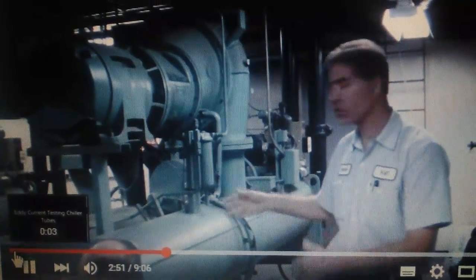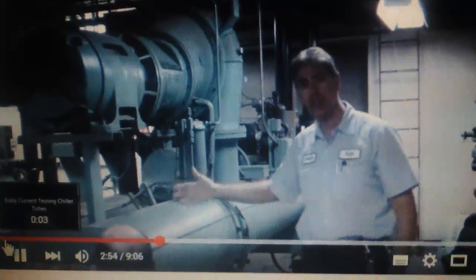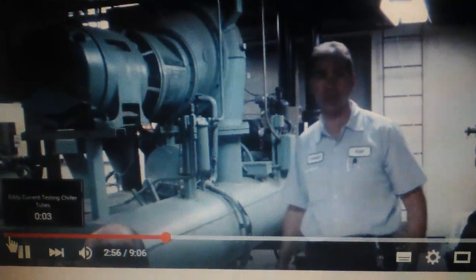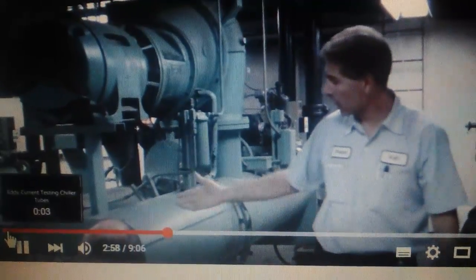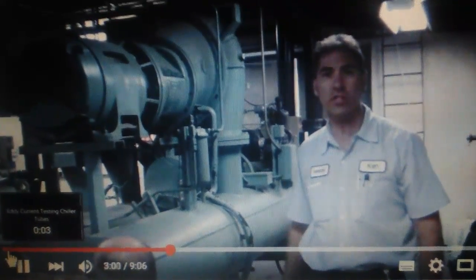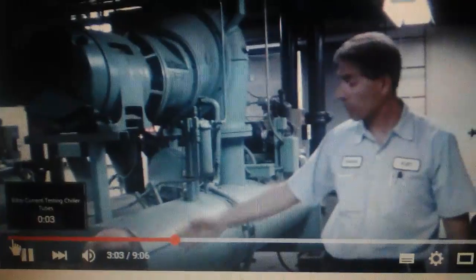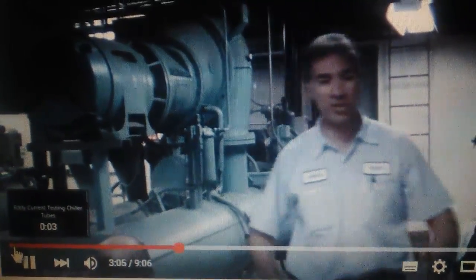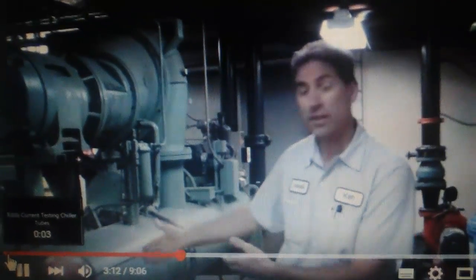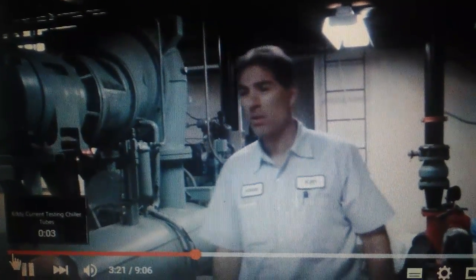And then due to the age, we're concerned about how long this particular chiller, which is running R11 refrigerant, will last. It's a little over 26 years of age. So we're performing an eddy current test here to see how the tubes are doing with 26 years of age. You know, how many more years can we get out of these tubes and out of this chiller? What is the life expectancy of the chiller? Some people say life expectancy is 25. We're already at that life expectancy, but you can push that out with good maintenance.